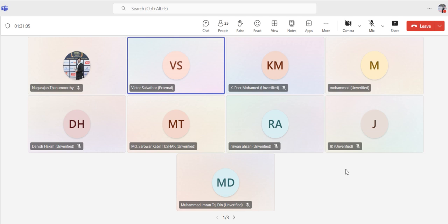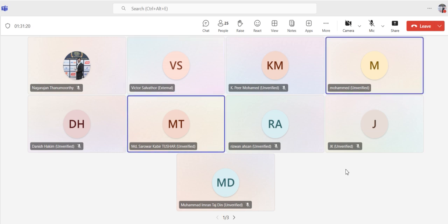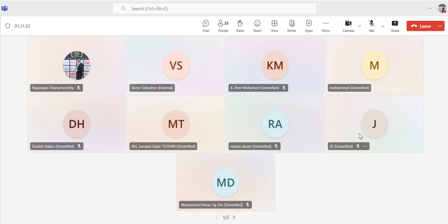So water cooled chiller means you have a reservoir and a cooling tower. That time you have to consider the minimum static height, based on the distance from the cooling tower to the system. But sir, cooling tower to the system means cooling tower to chiller height distance? No, you don't want to consider that distance.